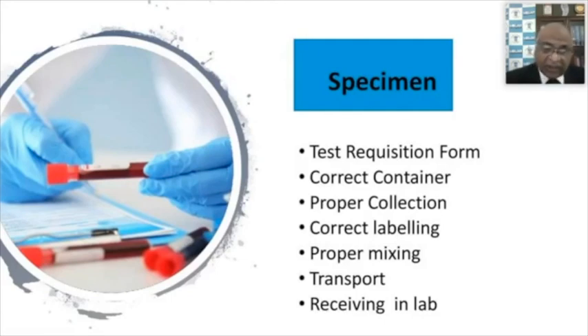All these things are okay, but our ISO 15189 is using lab acceptance testing for this activity. What is required, whether it is a simple reagent like some stain, Leishman stain, Ziehl-Neelsen stain, Gram stain, or some card test, or some quantitative parameters, we should have a documented procedure for lab acceptance testing, some acceptability criteria, then some evidence of actual performance of that activity. If we are generating instrument printouts, keep those in the record, and then these documents are approved by some authorized person, and they are allowing testing through this reagent for patient.